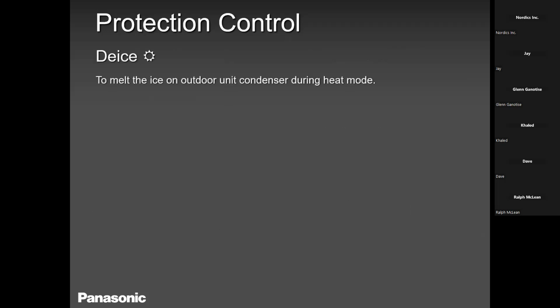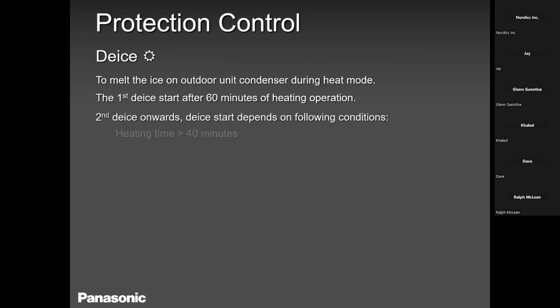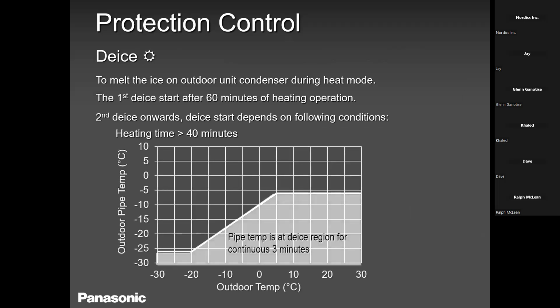Like I mentioned earlier about de-ice or defrost. So basically our first defrost cycle will kick in after 60 minutes. Our second will kick in after 40 to 45 minutes. And it will repeat that cycle off and on, depending on the coil temperature. Okay, so basically our defrost cycle is anywhere from 3 minutes all the way to 10 minutes maximum. So whichever brings the coil temperature to 26 degrees Celsius and above, that will terminate the defrost cycle.